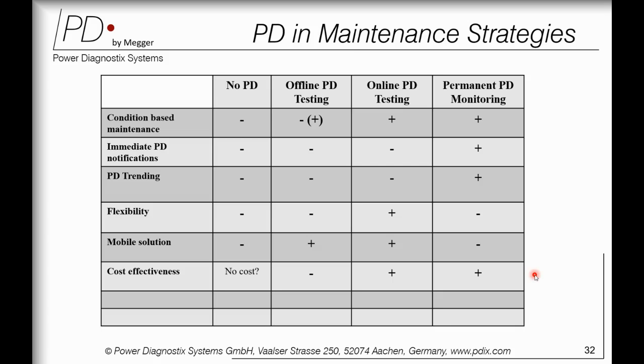strategies should be, right? If you don't do any PD measurement, there's no cost involved, but there is a very high risk of failure. Then there are three other methods. One is offline PD, which is only done during the commissioning charge test. The other is the online PD test, which is spot measurement. You go there, take the kit, and go to the various sensors. In this, you don't get any immediate PD notification. You cannot do PD trending, but you do get condition-based maintenance, flexibility, a mobile solution, as well as cost effectiveness.